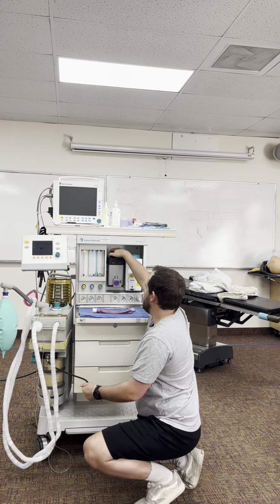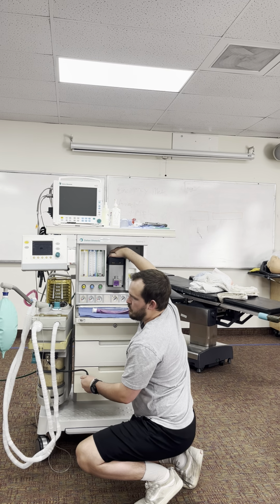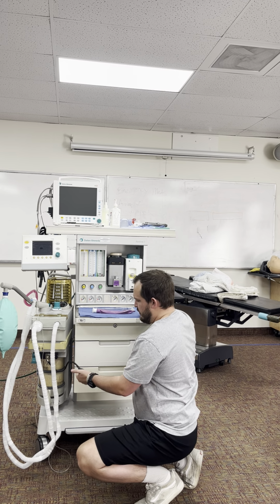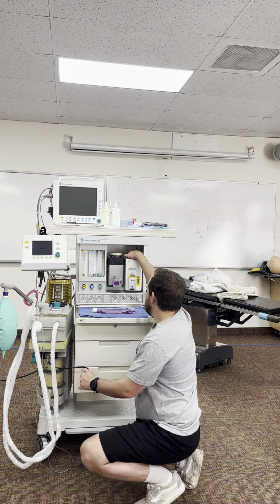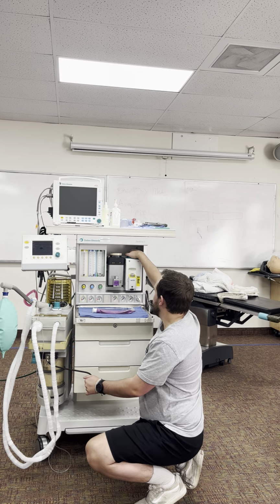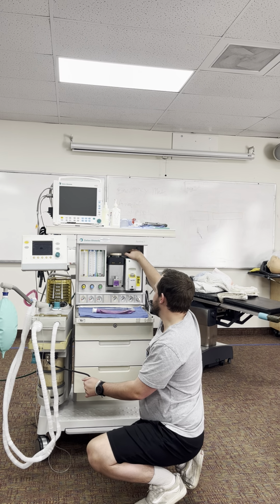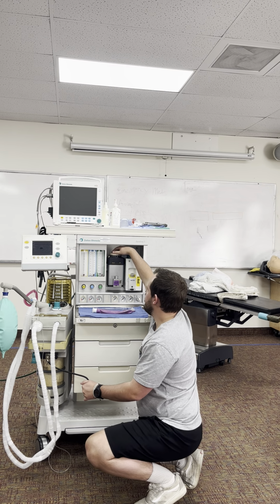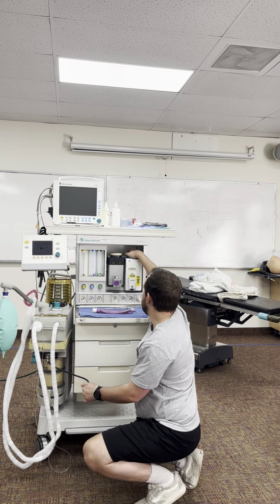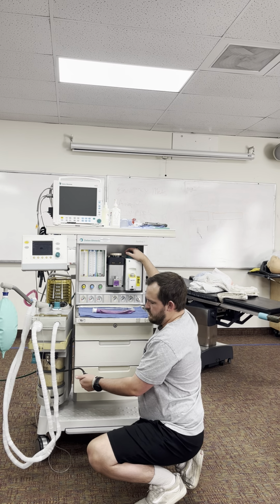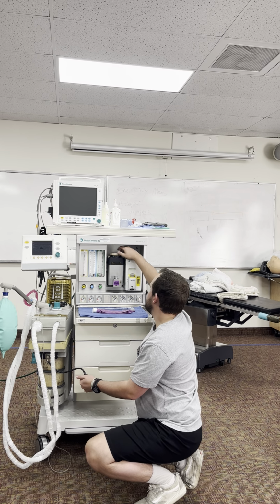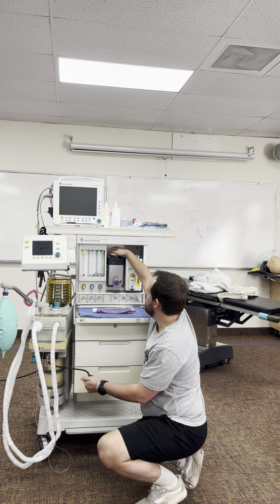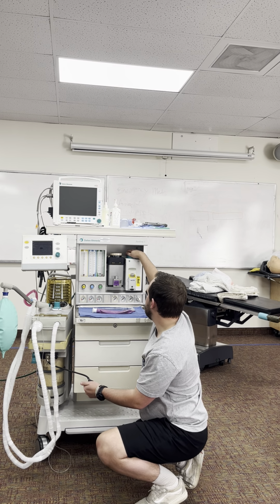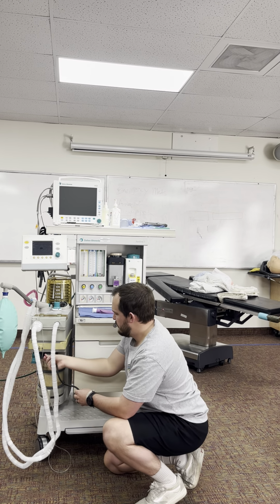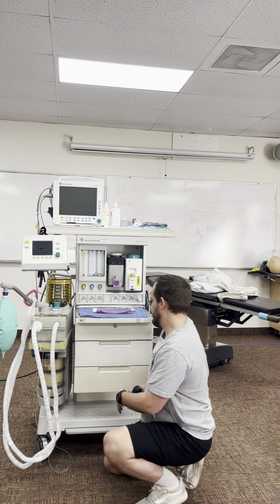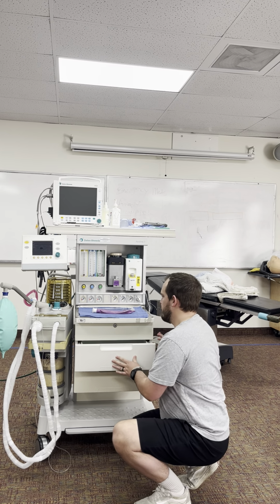Now I'm going to check my vaporizers the same way. I'm going to open up my ISO. It's open. Make sure it stays closed for 10 seconds. It does. And I'm going to check my interlock safety by trying to open up my SEVO. It doesn't, so that's good. That means the interlock safety works. Turn off my ISO. Now I'm going to turn on my SEVO. Do this again. It stays down for 10 seconds, and I cannot open my ISO, so that is another safety pass. So I'll disconnect that, or sorry, turn it off, disconnect, close my valve, put it away.